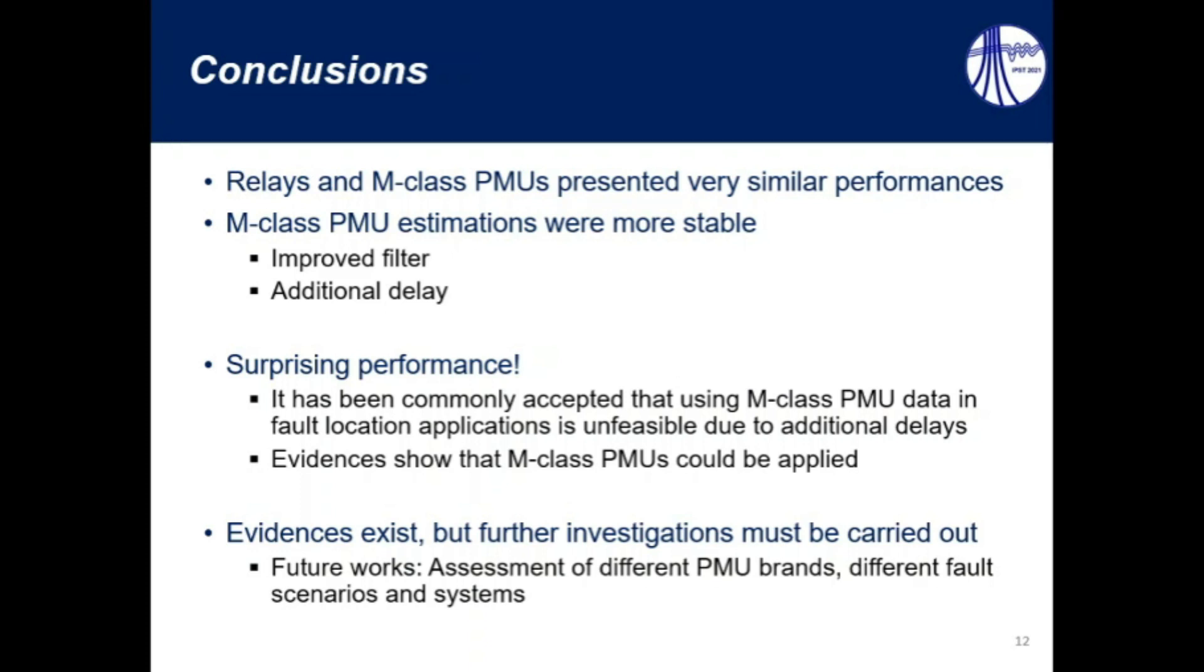Thus, as conclusions, we can say that relays and M-class PMUs presented very similar performances. The M-class PMU estimations were more stable. Indeed, they have improved filters, but they have also additional delays, in such a way that this was a surprising performance for us. Indeed, it has been commonly accepted that using M-class PMU data in fault location application is unfeasible due to the additional delays. But evidences shown in this paper demonstrate that M-class PMUs could be applied in these evaluated scenarios.